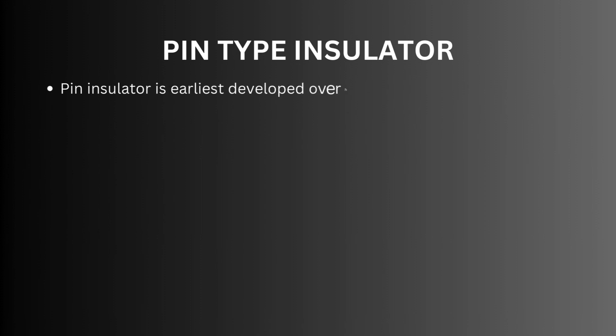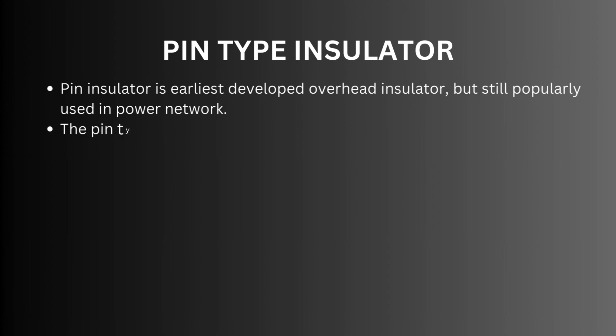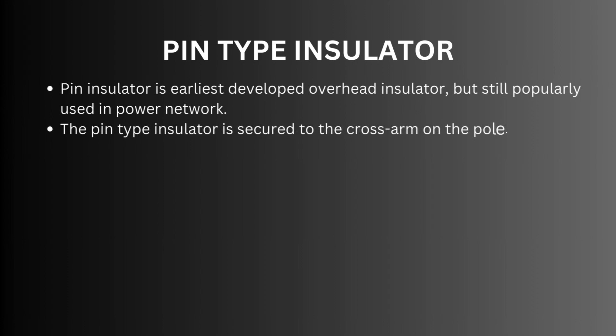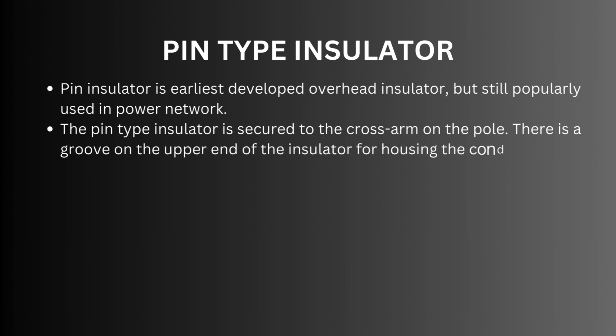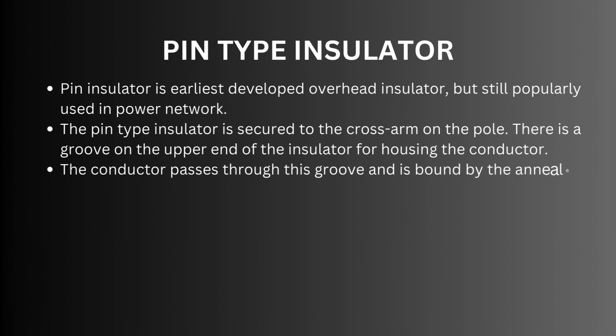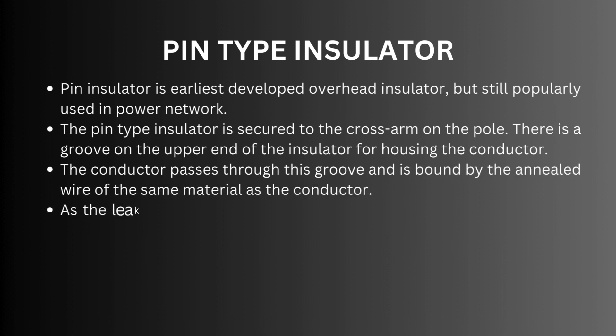Pin insulator is the earliest developed overhead insulator but is still popularly used in power networks. The pin type insulator is secured to the cross arm on the pole. There is a groove on the upper end of the insulator for housing the conductor. The conductor passes through this groove and is bound by annealed wire of the same material as the conductor.